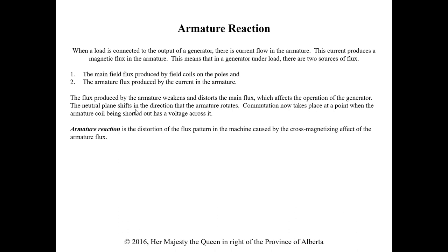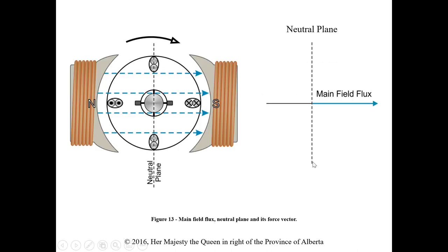The armature flux distorts the main flux or field flux, which affects the operation of the generator. The neutral plane shifts in the direction that the armature rotates. Commutation now takes place at a point where the armature coil being shorted has voltage across it. The whole point of locating the brushes at the neutral plane was to avoid arcing — but with armature reaction, the neutral plane shifts, and now contact is being made outside the zero-volt point, causing arcing, sparking, and heat. Armature reaction is the distortion of the flux pattern caused by the cross-magnetizing effect of the armature flux.